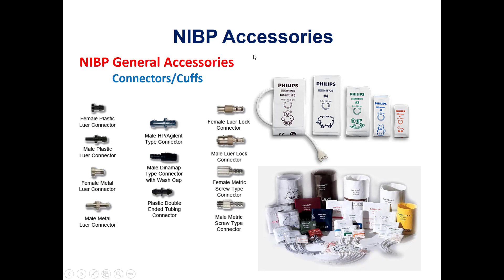The non-invasive blood pressure accessories include different types of connectors manufactured by different manufacturers, as each manufacturer has its own connector type. The non-invasive blood pressure cuffs manufactured by Philips are disposable, available in different sizes: 5, 4, 3, 2, and 1. GE Healthcare also produces non-invasive blood pressure cuffs in both disposable and reusable types.